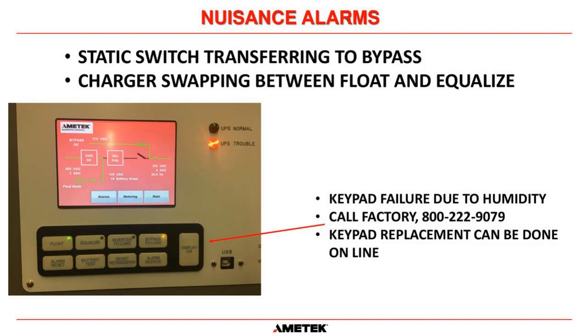So it was easy. When we first saw this happen, we pulled the connector out of the control board, or the display board, right here inside the cabinet. And if we had clearance to do that, we'd do it with the machine online. It will not initiate transfers, things like that. So we've been able to disconnect it until we sent out a new keypad.